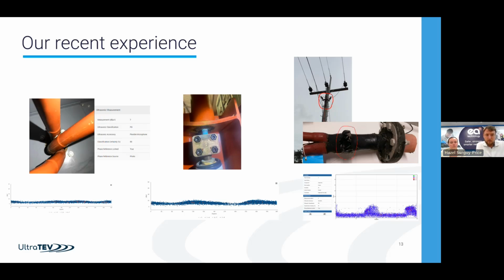The first example on the left-hand side is a cable crutch. The cores have been crossed, there's high stress, and you can see some white compounds starting to build up between two of the phases. That white compound is partial discharge, and the graph below is the output from the instrument showing activity related with the 50 Hertz phase - you're seeing a couple of humps in that, so there's two phases involved in the discharge.